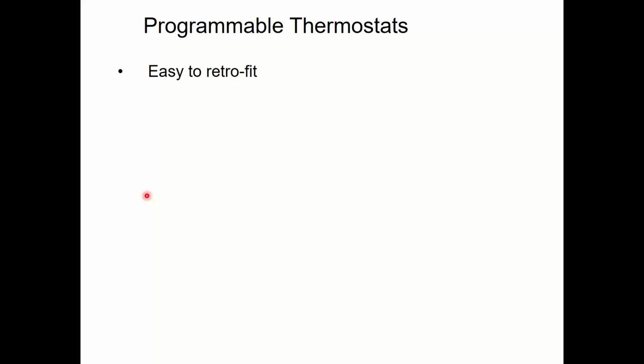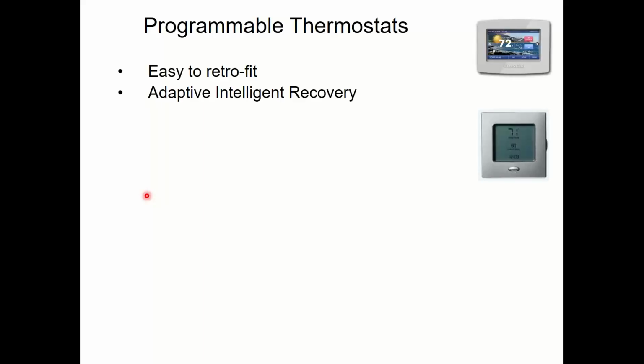They're very easy to retrofit, programmable stats. It's not a challenge at all. The biggest issue is sometimes you might need a couple extra wires, like a common wire, but we have ways around that. One of the features you may want to utilize is adaptive intelligent recovery. It's also called smart recovery. It's called optimal start. There are different names for it from different manufacturers. What it means is it looks at the previous run history for the past couple days and decides how long it took to heat or cool this building up the last couple mornings, and then it uses that to adjust things now.